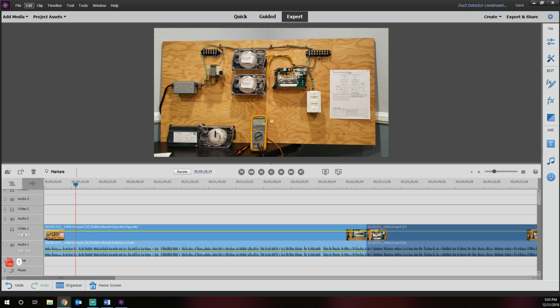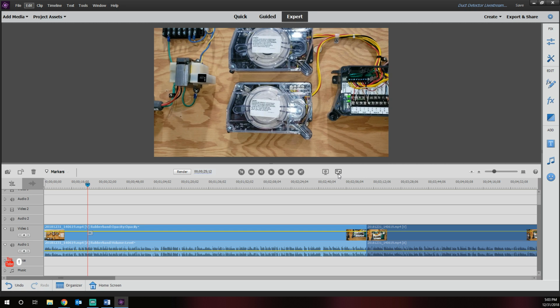The trouble condition is an instance where, depending on the detector, this particular one can be set up to initiate a trouble condition if you remove this cover. Say someone was doing work on the duct detector and left the cover off. It would initiate a trouble condition, telling the alarm company something's wrong, because if the cover is left off, theoretically it wouldn't sense smoke properly.